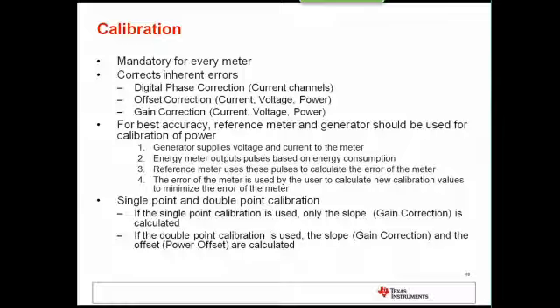Whenever you perform calibration for best accuracy, you should always use a generator and reference meter. The generator supplies the voltage and current to the meter. The meter uses the voltage and current and, based on that, calculates power and outputs pulses. The reference meter uses these pulses to determine the error of the meter. Once this error is calculated, the user can then update the calibration parameters as necessary. There are two types of calibration that can be done, single point and double point. In single point, only the gain is calculated, and in double point, the gain and the power offset are calculated.